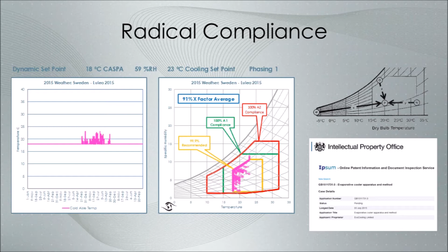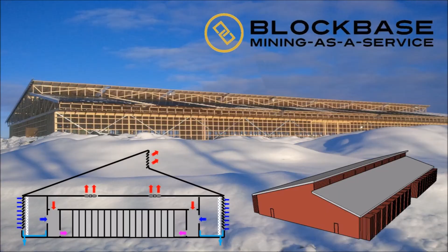Here's another one we should be commissioning over the next few weeks, BLOCKBASE. That's a 16 megawatt building, once again in Sweden. Huge building, air changes every 10 seconds. Air going around that building at 30, 40 kilometers an hour, down to minus 40. That happens to be a wooden construction building, and that's based just on pure fresh air around what we're calling our cloud cooler.